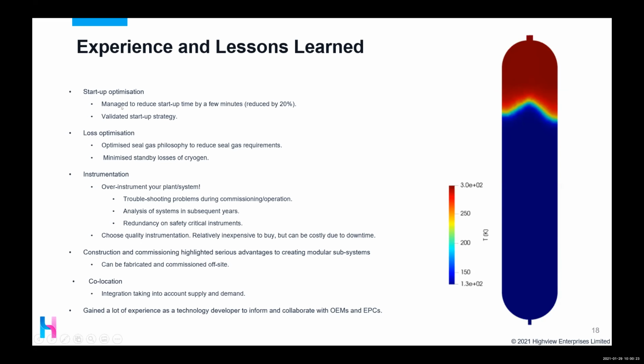We validated our startup strategy: using the cryopump as the main power governor, and then using the cryopump and inlet guide vanes, or on a larger scale plant, inlet valves, as a means of precision control for a speed ramp. Together we were able to validate how to start this plant, particularly as it's a Rankine cycle in sliding pressure operation, a little different to how a steam turbine would work in a steam plant.